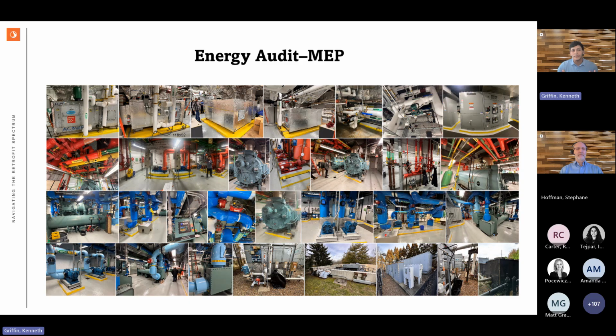Our energy audit for the MEP system, we went through a walkthrough of the whole building. We got a real feel for the chiller plant, the boiler plant - this is a steam boiler plant - and the cooling towers. I wrote down all the nameplate data so we could understand the design performance of these systems. We put together our mechanical drawings based on our walkthrough and the existing drawings, which gave us an idea of what we were dealing with in terms of a mechanical system and the distribution as well.